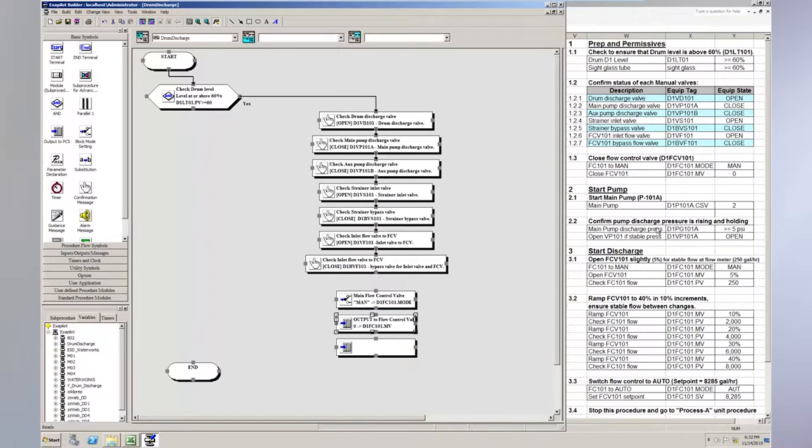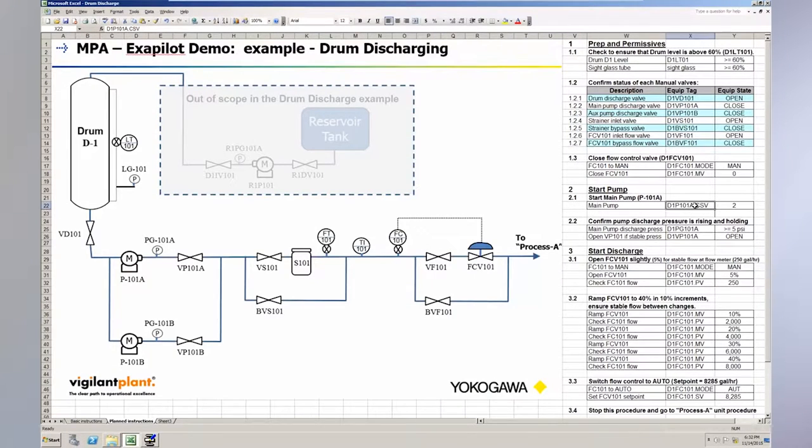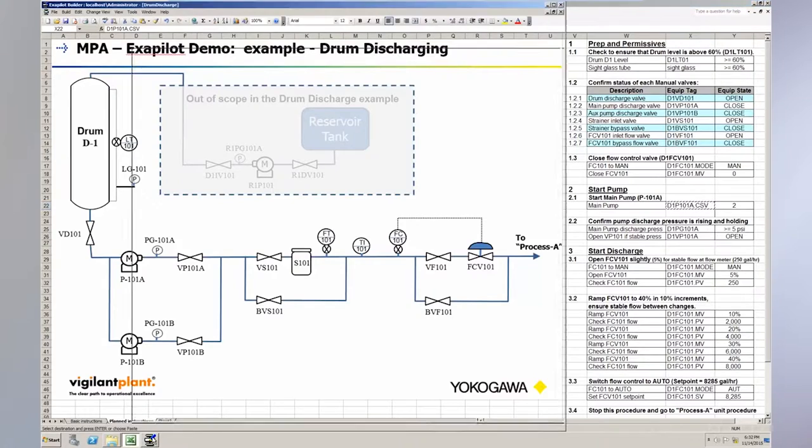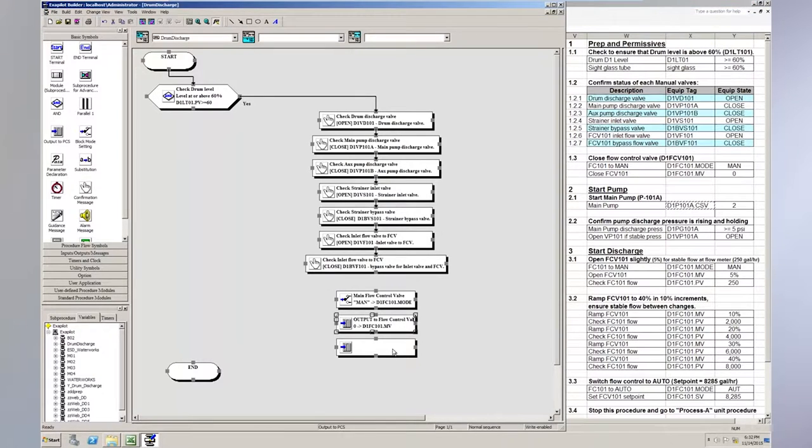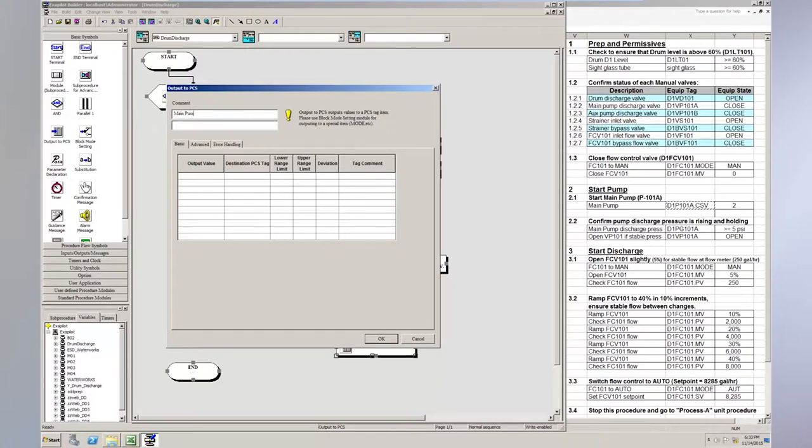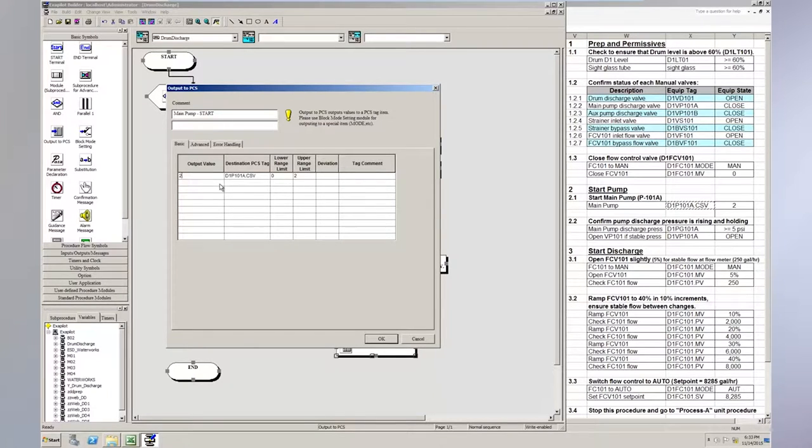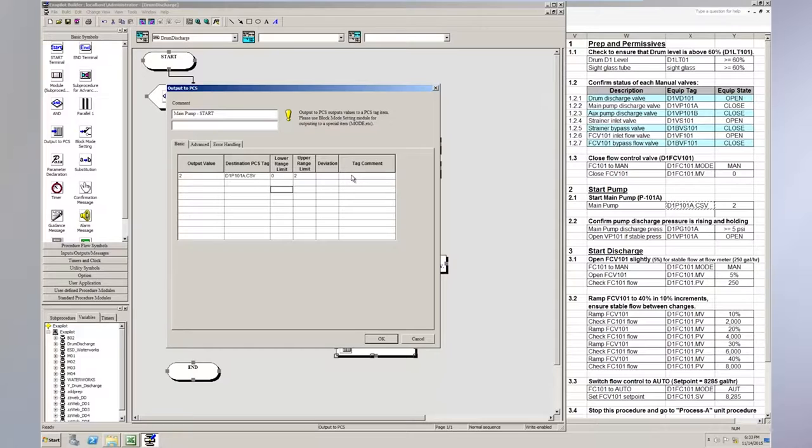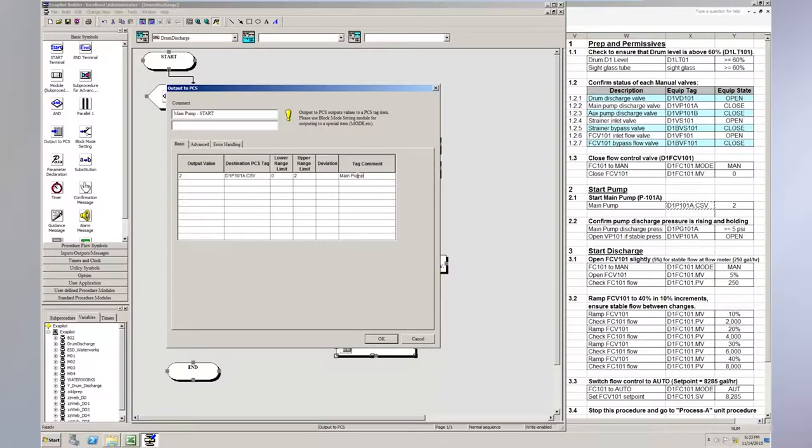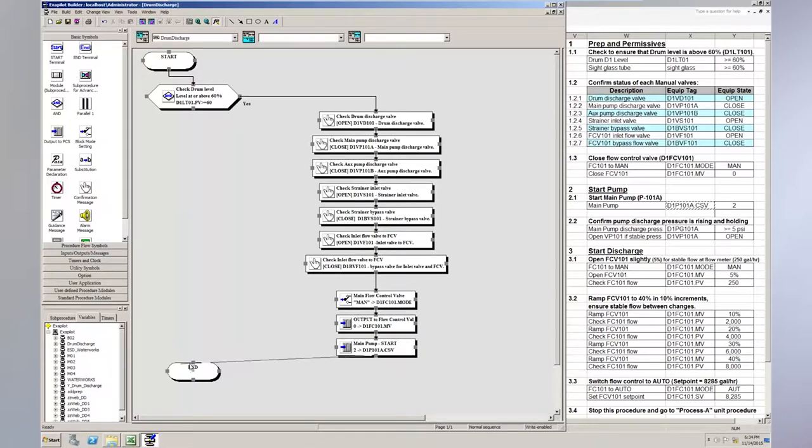And then the next thing we can do is start the pump. Once the flow control valve is closed, we can then write to this pump. And it's a little different. I don't need the mode on the pump because the pump output is not a PID loop. It's a digital composite or a switch. So this is the main pump start. And we can put that tag there. In this case, this DCS uses a 2 to turn on the switch. Your DCS may use a different value or different enumeration text named for that. And you just need to type in whatever is appropriate for your control system. And then I'm going to skip the ramping procedure. And really, my main goal here is just to show you how easy it is to perform reads and writes and make decisions within the procedure.